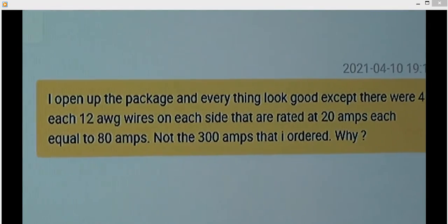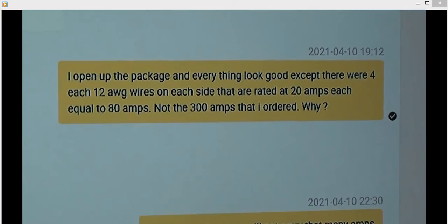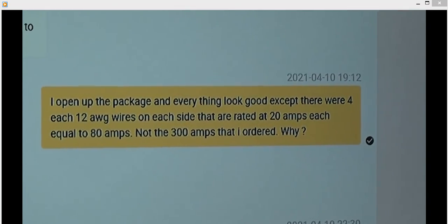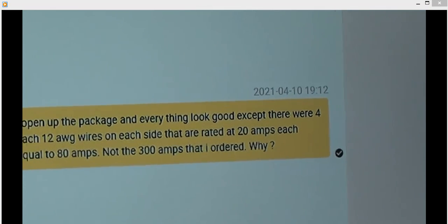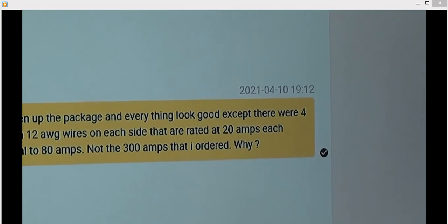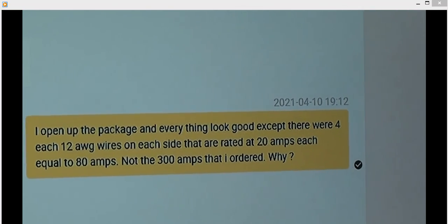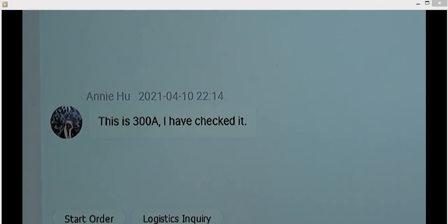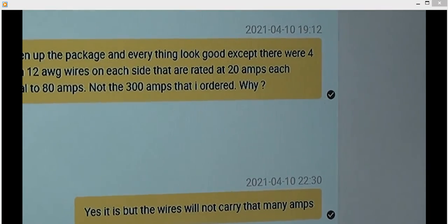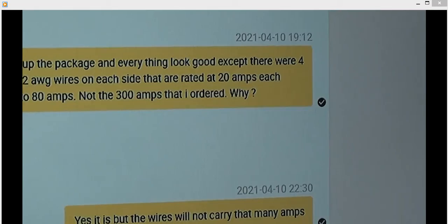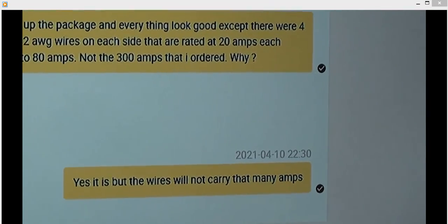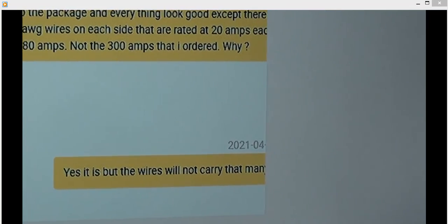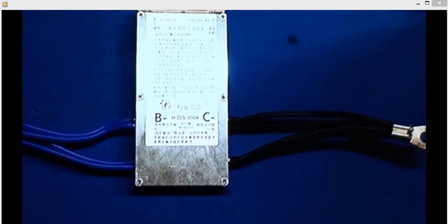I opened the package up, and everything looked good except there were 4 each 12 AWG wires on each side that are rated at 20 amps each. Equals 80 amps, not the 300 amps that I ordered. Why? This is a 300 amp. I checked, but yes, it is, but the wires will not carry that many amps. So I'm believing that they sent me the right one, and that's because the sticker on the back says it's rated at 300 amps.